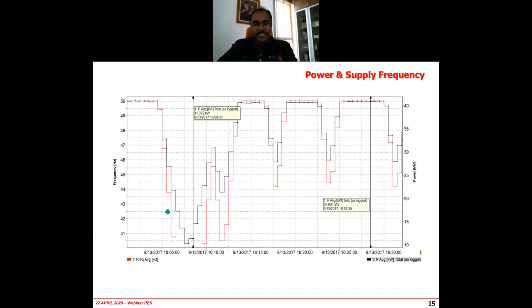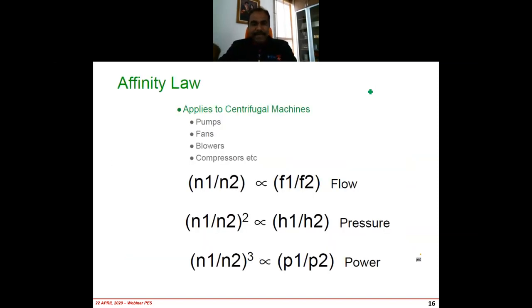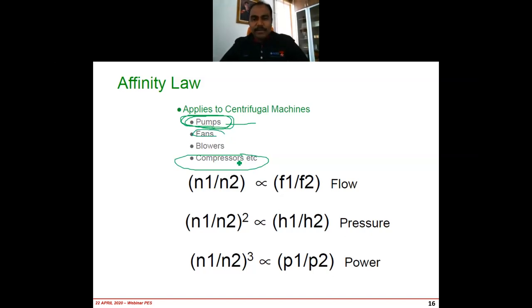As everyone will know, as far as the induction motor is concerned, we change the supply frequency to change the speed of the induction motor. Every time we change the speed, we see that power is also proportionally reduced. In fact, this is the mechanical law, the fan law or pump law, the affinity law. It always applies to most systems. In Malaysia, or most countries in the world, almost 70% of our load is pump load, followed by fan, followed by compressor. So all of them will comply with this affinity law, because all of them are centrifugal machines.